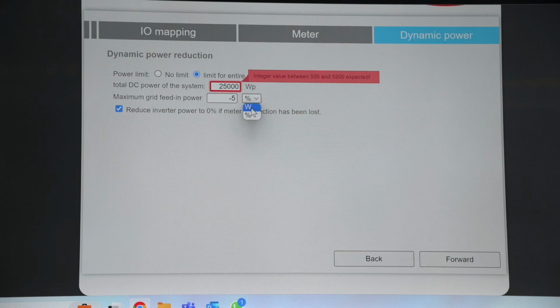What I always say is to use a negative percentage, as that way you are always drawing from the grid itself and you're never riding at that absolute zero wattage that you are pulling from the grid itself. If you are slightly pushing back into the grid, some of the meters are sensitive again. It all depends. That's why I normally recommend doing a negative value, so that way you're always drawing from the grid and never riding dangerously.